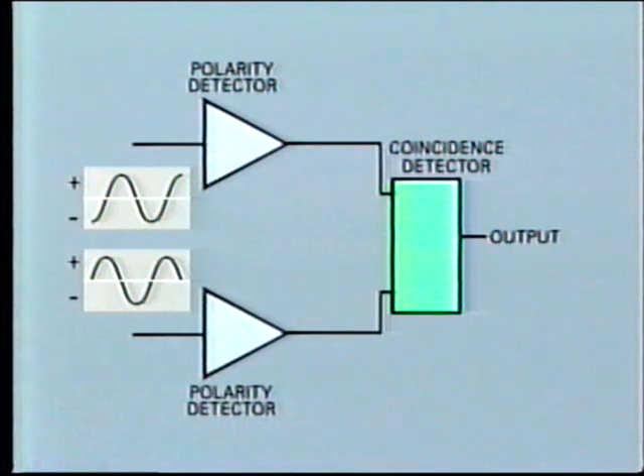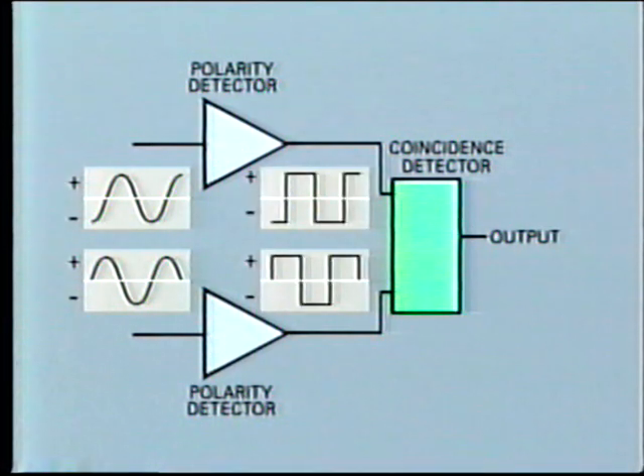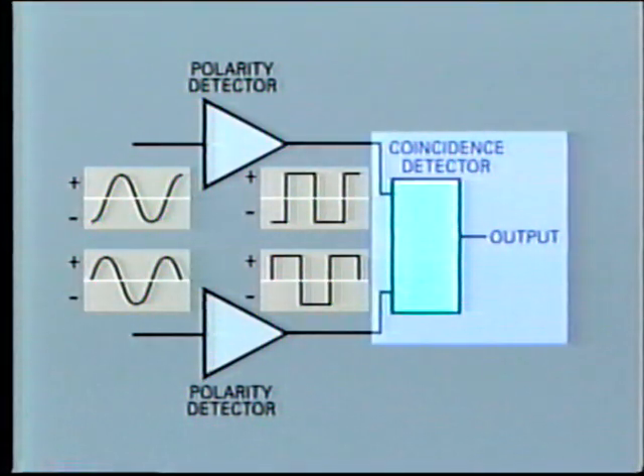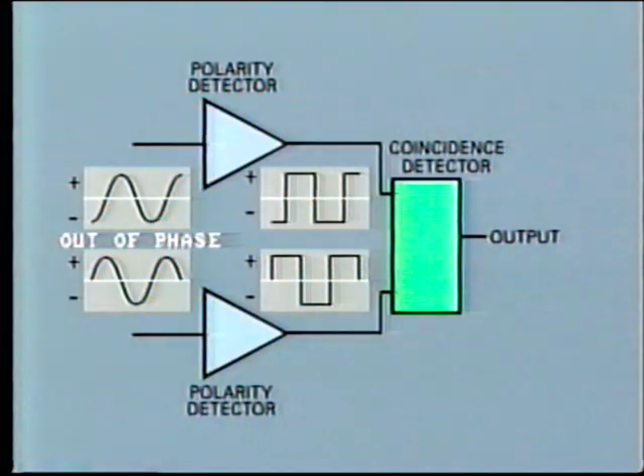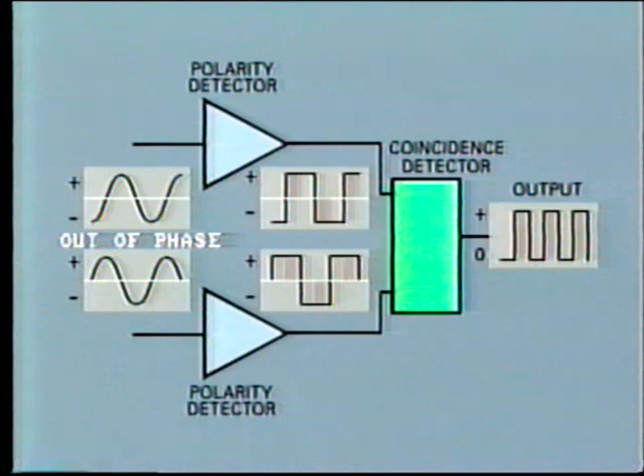In this particular phase comparison circuit, the square wave output from each polarity detector is compared in the so-called coincidence detector. Supposing the two sine waves are slightly out of phase, the respective square waves will look like this. The detector will only provide an output signal when both incoming signals are positive or both are negative. There is no output when they are of a different polarity. The resultant output is a series of DC pulses like this. The time period of each DC pulse depends upon the phase angle between the two inputs.